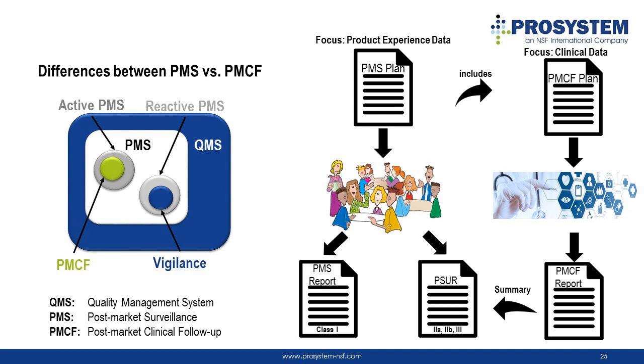As I already mentioned, the PMCF is part of the proactive PMS activities, and therefore the PMS plan must include the PMCF plan or a reference to the PMCF plan if you decide to have two separate plans. Based on the PMCF plan, the manufacturer will perform the activities and generate the PMCF report, and the PMCF report is the input for your PSUR or PMS report. For Class 3 and implantable devices, the PMCF report should be updated annually.